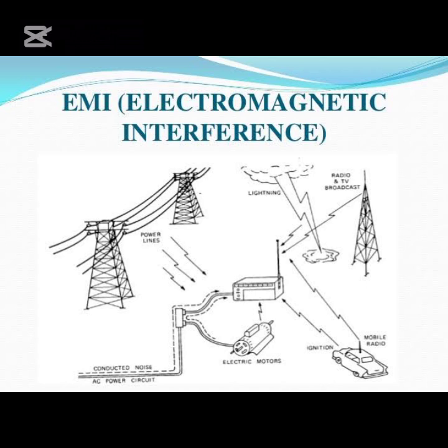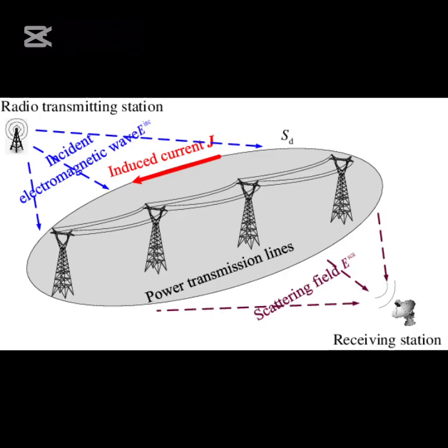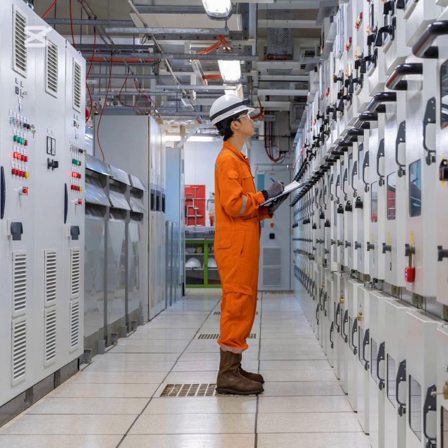The high-frequency electromagnetic radiation emitted by corona discharge can interfere with electronic devices, causing malfunctions or data corruption. 7. Power quality issues. Corona discharge can cause power quality issues, such as voltage fluctuations and harmonic distortion. The ionization of air around conductors can cause voltage fluctuations and harmonic distortion, affecting the quality of power transmitted.